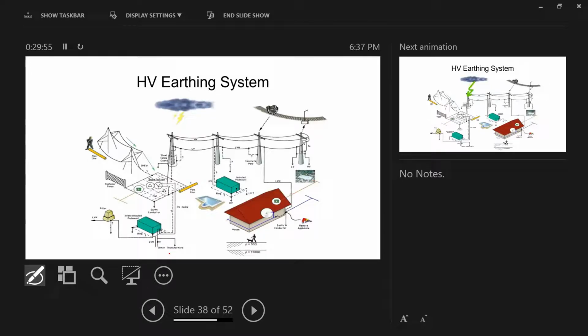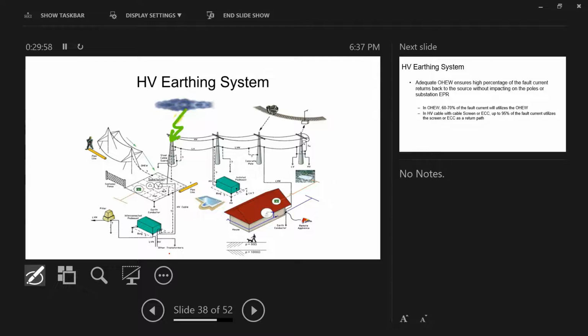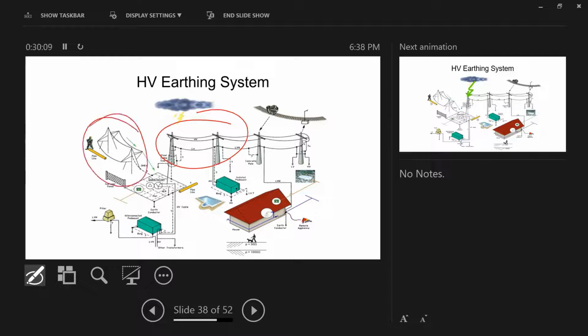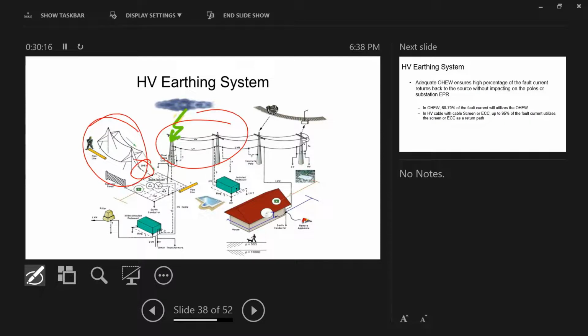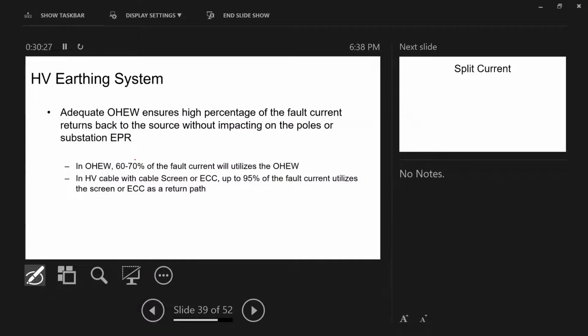Now, as you can see, everywhere I have earthing, everywhere. I put this scenario and I put the other scenario. One of them has no overhead earth wire, one of them has overhead earth wire. See, they put in here overhead earth wire. If you have a lightning strike without overhead earth wire, your actual conductor might get damaged. So you need to have some sort of protection system. This is based on a lot of case studies. If you design a proper overhead earth wire, it will take 60 or 70% of your fault current. So imagine someone tells you, design this properly and it will take up to 70%, sometimes more, of your fault current.